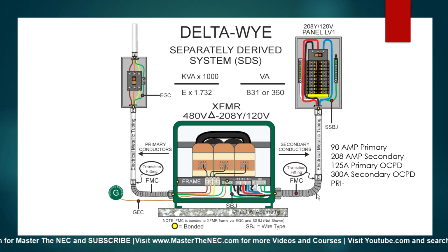Now we're going to size this supply side bonding jumper in accordance with 250.30(A)(2), which ultimately is going to tell us to go to 250.102(C), but it's going to be based on these conductors right here. And these are called the derived conductors because they're derived from the secondary of this transformer. If you think of derived as another word for newly born, then these newly borns right here, we're going to size those.